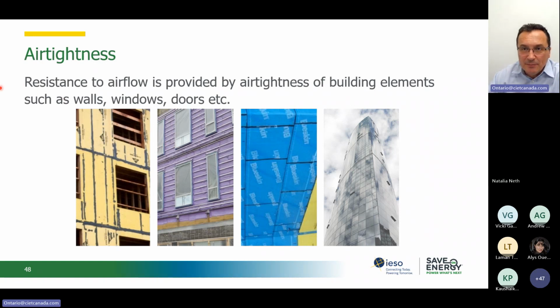So whenever we do this type of improvement in the building efficiency, in the building envelope efficiency, we would like to address the air tightness. We would like to make the building tighter. Some of the examples we see here are showing the type of retrofits we are doing: air sealing, increasing the insulation for the opaque building envelope, and making sure that windows are installed properly with the air tightness required. And if possible, we want to verify the success of this retrofit, which is aimed at increasing the air tightness, with a blower door test or thermography.